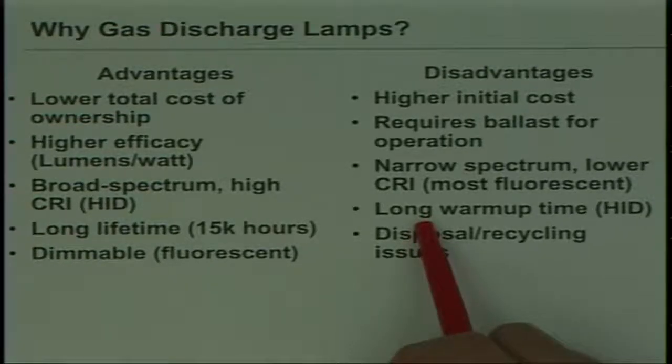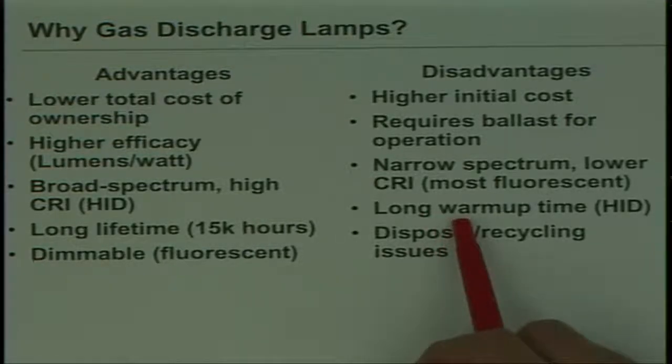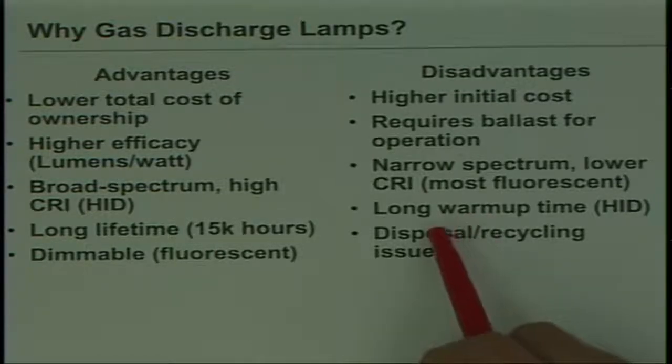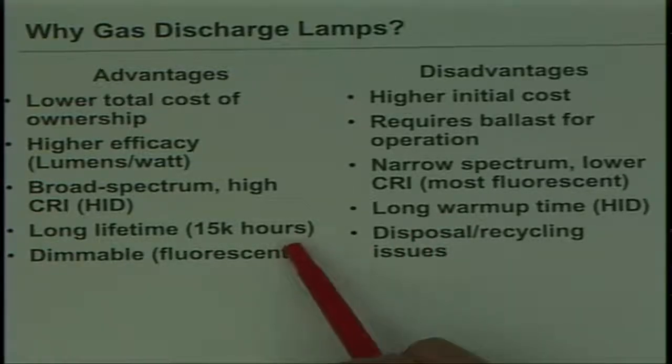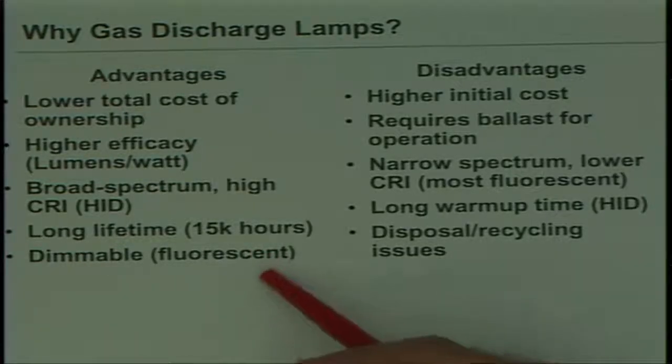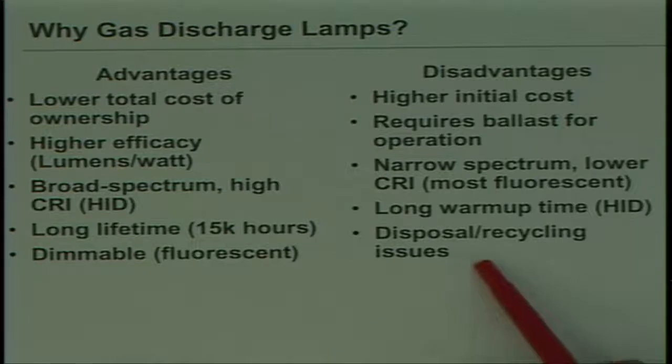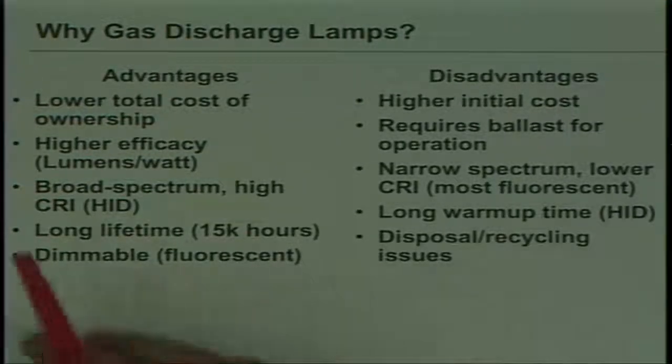Some of these take a long warmup time. Fluorescent is only fractions of a second. There's a tradeoff there. For the rapid start, you get less lifetime. With HID, they take very long, maybe five minutes to fully warm up. And when they're hot, they're very difficult to restart. Overall, you should get longer lifetime. Again, this depends not only on the lamp but also on the electronics and the environment they're operating in. Fluorescent and to some extent HID are dimmable, which gives you the advantage that from a system standpoint, you can lower overall facility operating costs. And there's disposal and recycling issues because they both contain a certain amount of mercury.